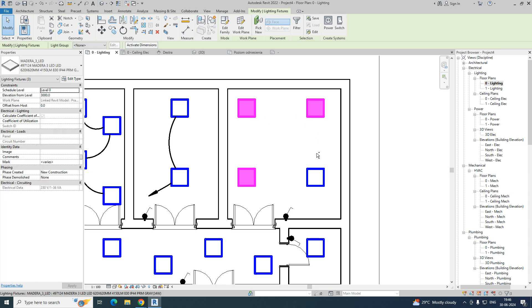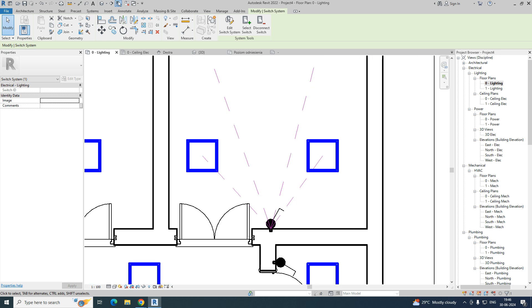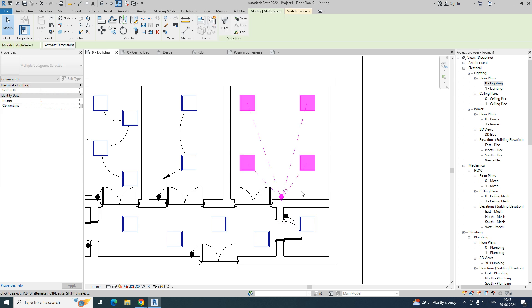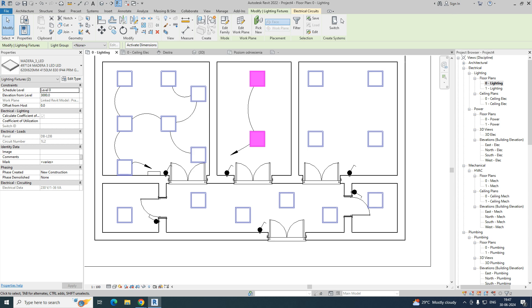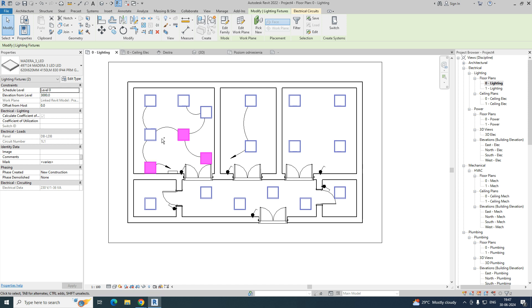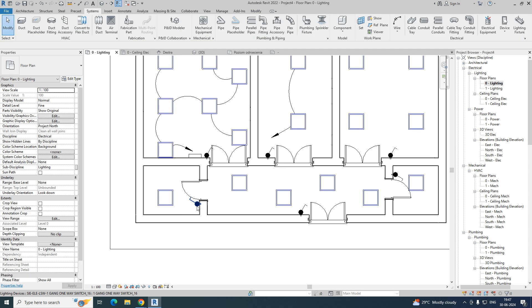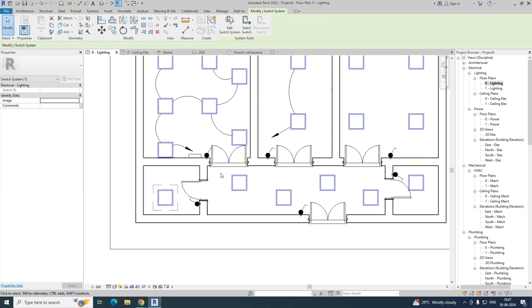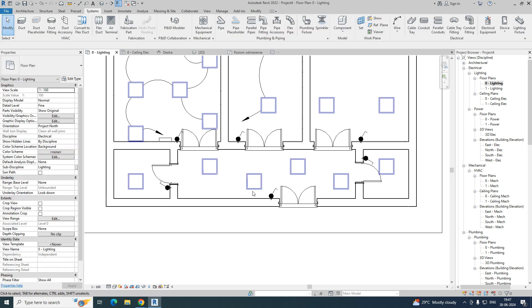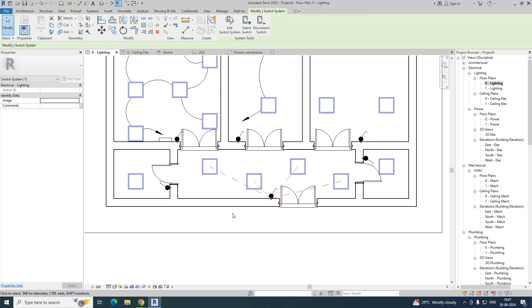To assign the switching system, select the lights, hold the Control key, and choose the Switching System option, then select the switch. You can see it shows which switch is controlling how many lights. Use the same process for the other groups — select the lights, give the switching system, and select the corresponding switch.